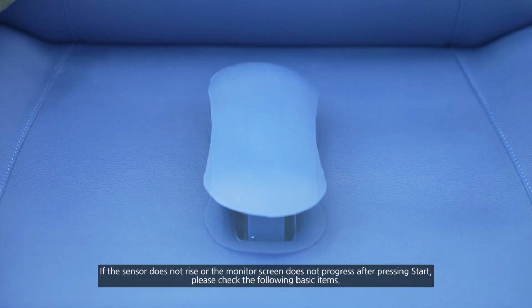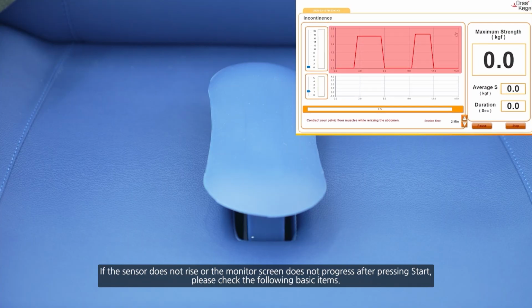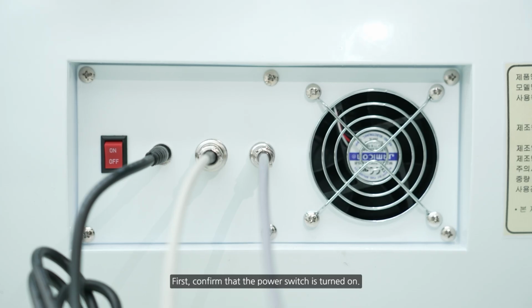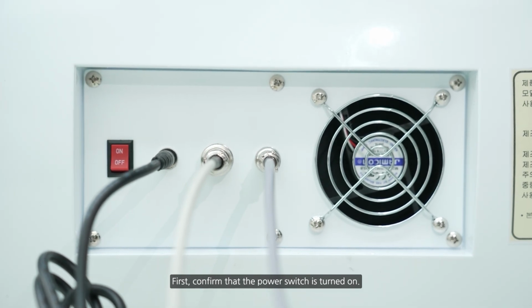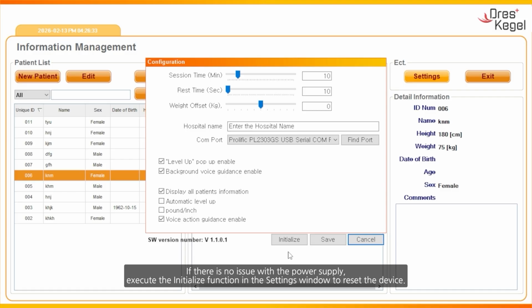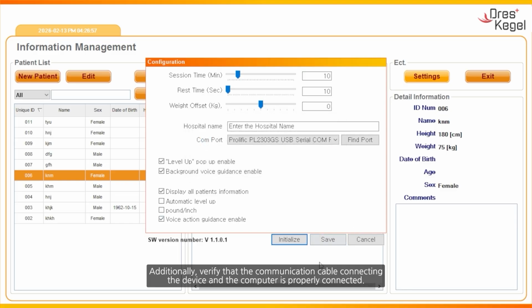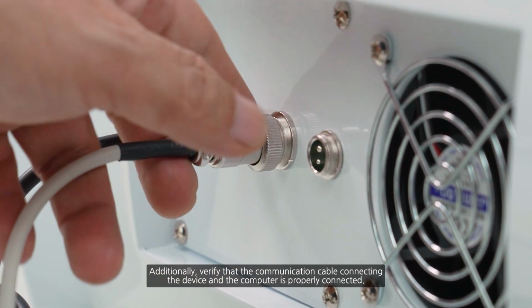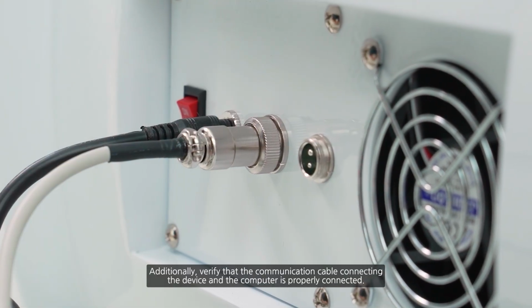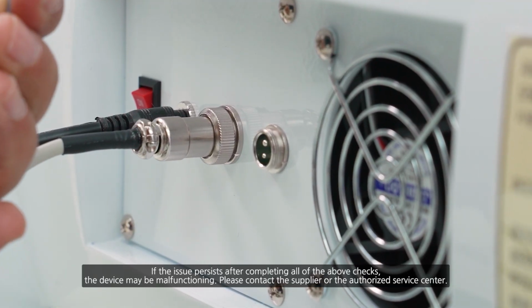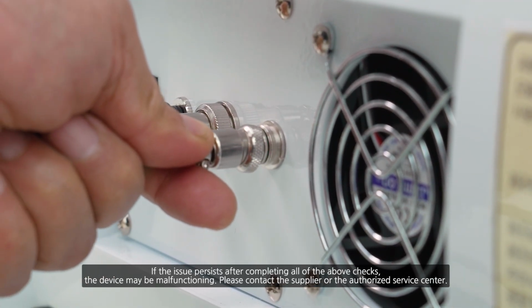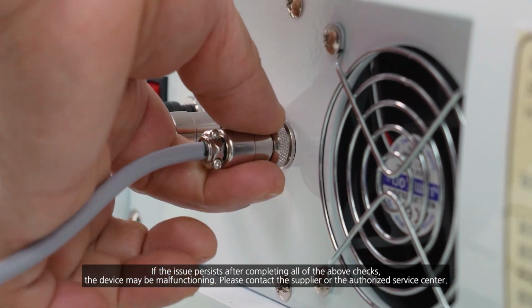Number 8-7. When the sensor does not rise and the monitor screen does not progress after pressing Start. If the sensor does not rise or the monitor screen does not progress after pressing Start, please check the following basic items. First, confirm that the power switch is turned on. If there is no issue with the power supply, execute the initialize function in the settings window to reset the device. Additionally, verify that the communication cable connecting the device and the computer is properly connected. If the issue persists after completing all of the above checks, the device may be malfunctioning. Please contact the supplier or the authorized service center.